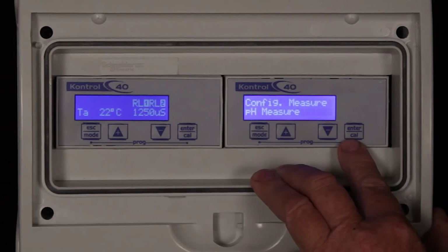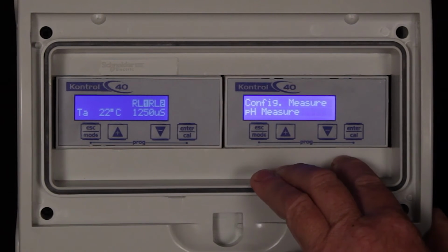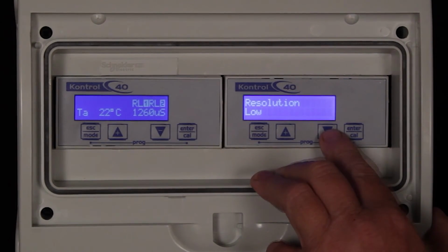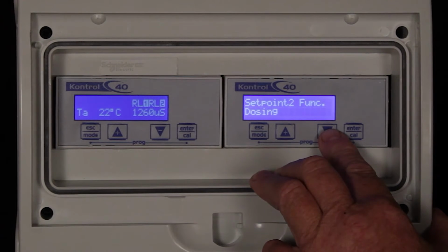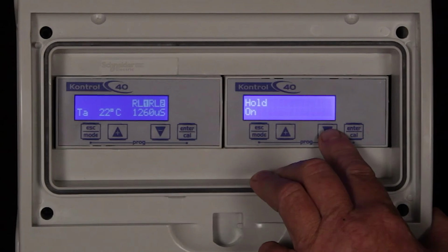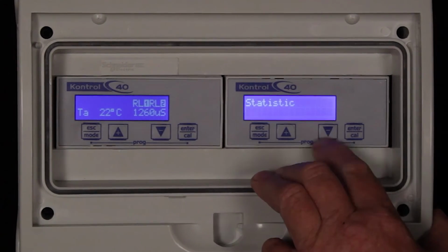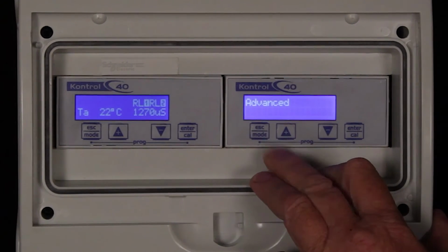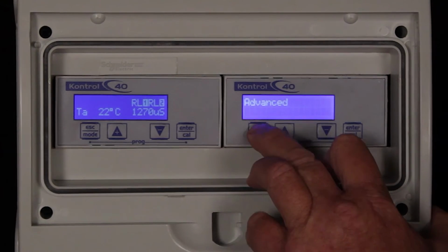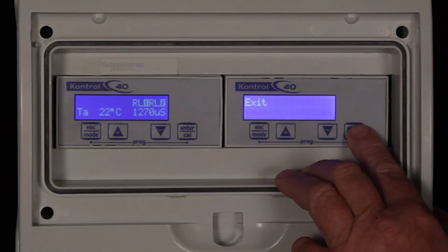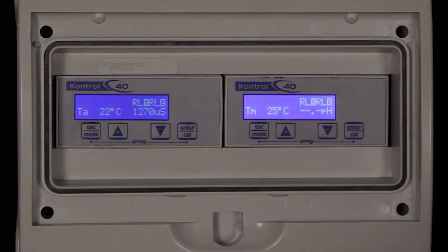In the advanced menu, config measure is set to measure pH and the resolution is set to low. Setpoint 2 is set for dosing as well, but is not used in this case. Hold is switched on. Calibrate is left on. And the pH controller is now configured. Press the escape mode button until you get to the exit and save message. Now press enter to save all changes.